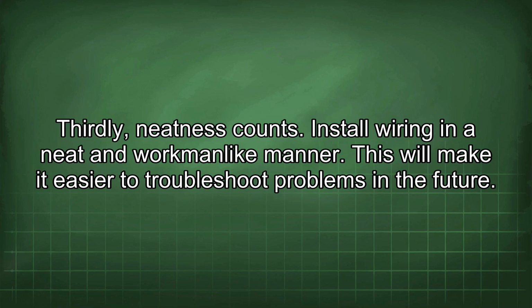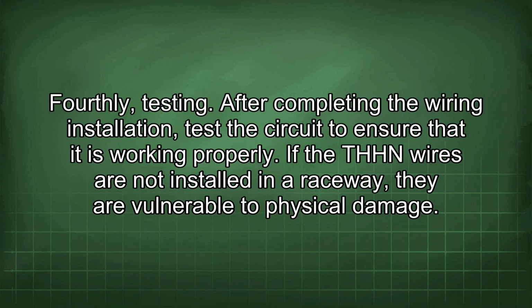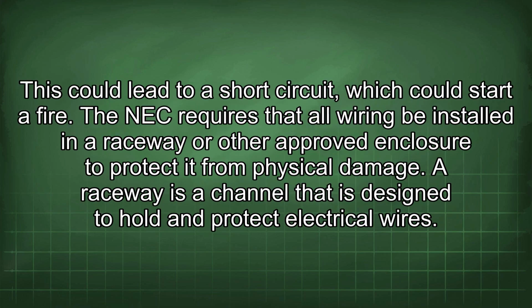Thirdly, neatness counts. Install wiring in a neat and workmanlike manner. This will make it easier to troubleshoot problems in the future. Fourthly, testing. After completing the wiring installation, test the circuit to ensure that it is working properly. If the THHN wires are not installed in a raceway, they are vulnerable to physical damage. This could lead to a short circuit, which could start a fire.